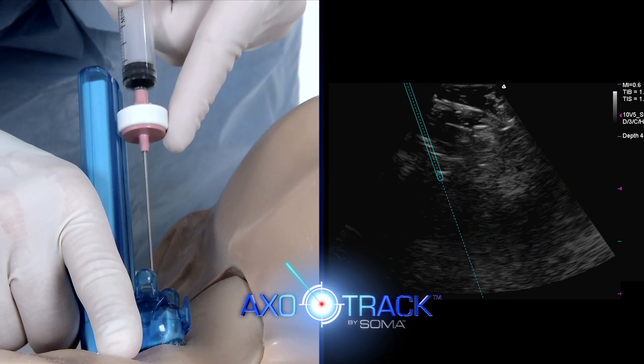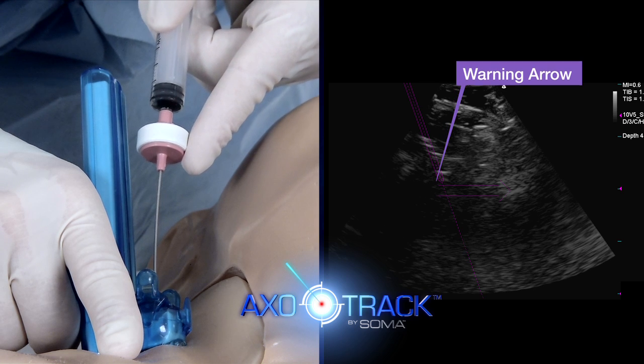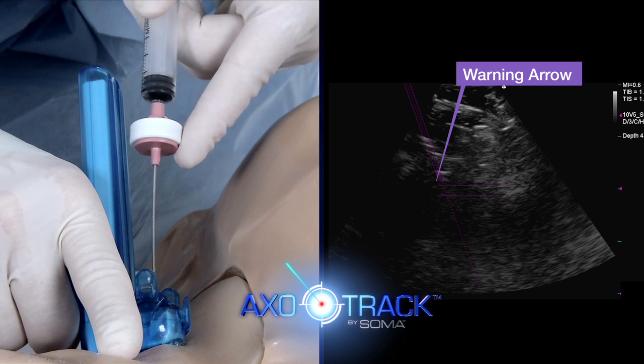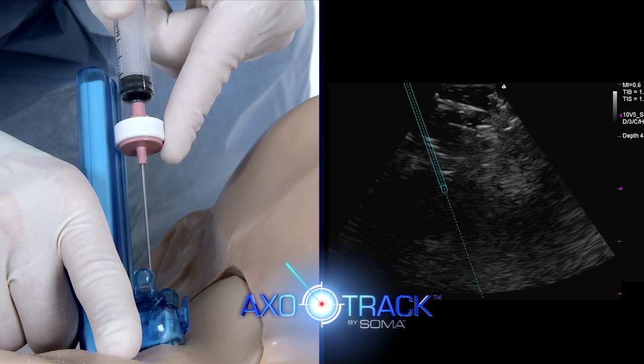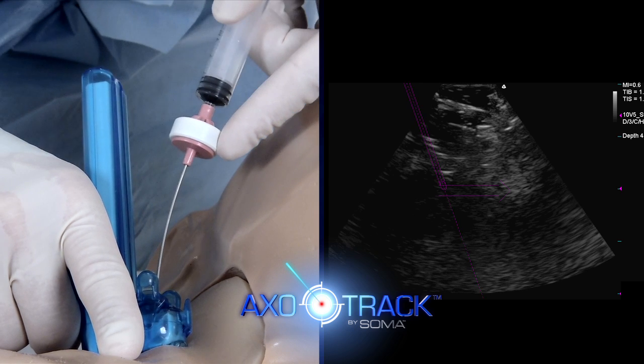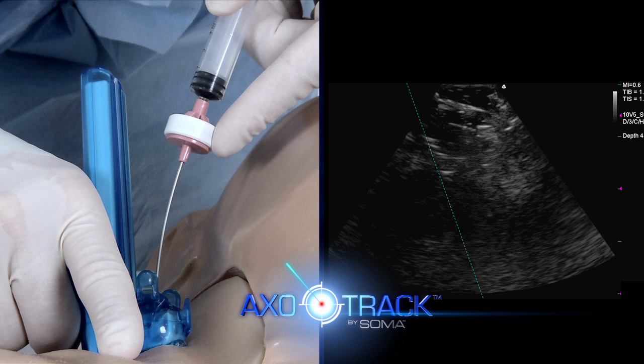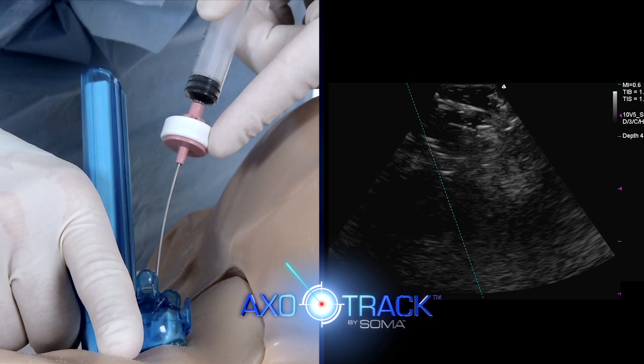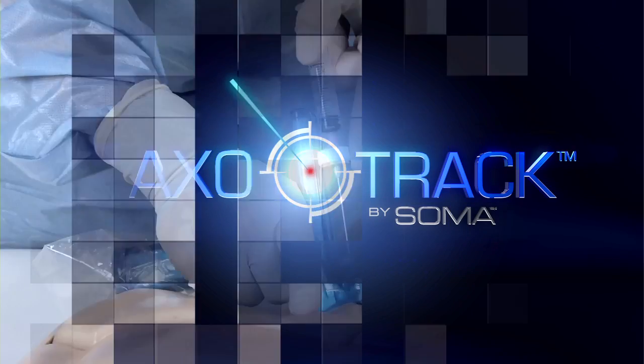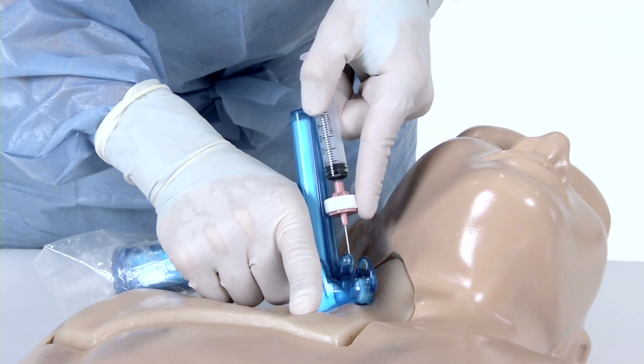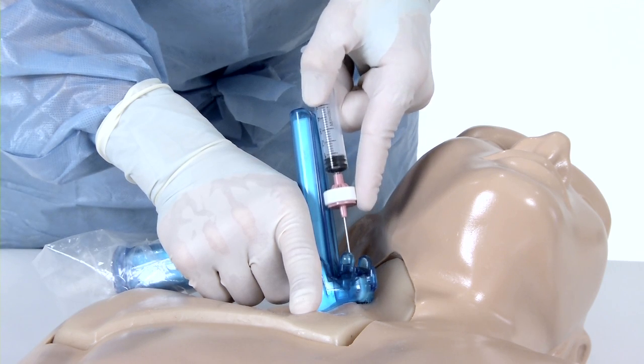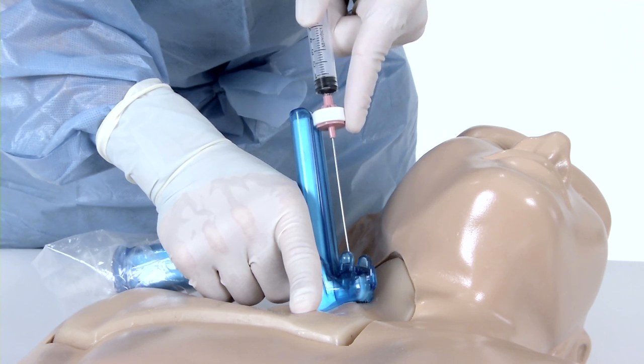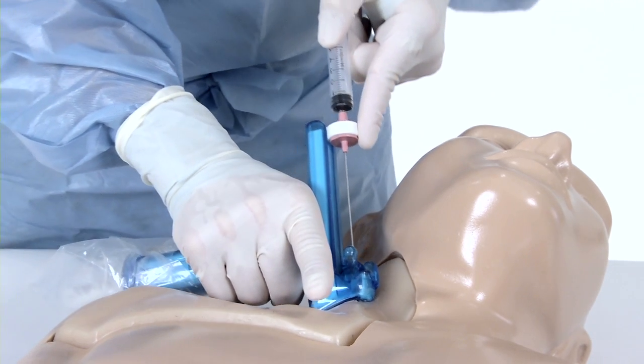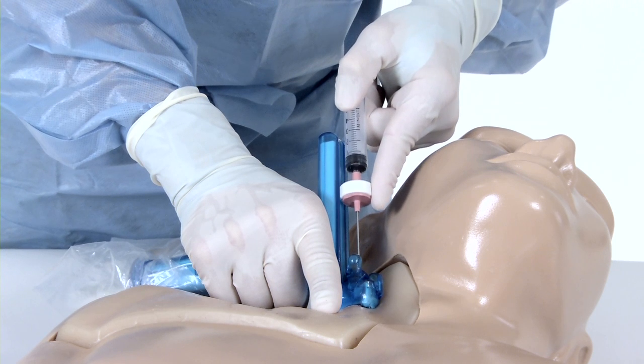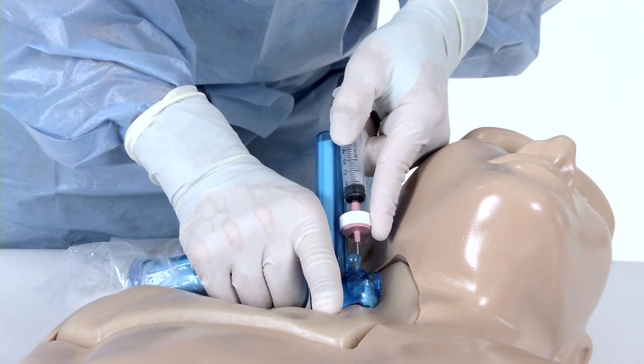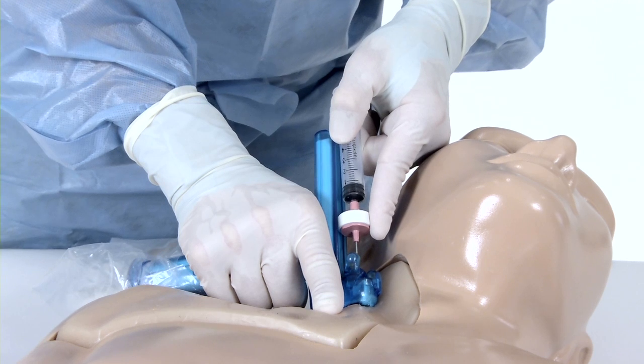If the magnet is bent away from the magnet rail, a bold warning arrow will appear on the sonogram, indicating that the magnet should be returned to its proper location. If the needle is bent too forcefully away from the magnet rail, the virtual needle will disappear completely, preventing continuation of the procedure. The practitioner should not attempt to reposition the needle or target line without withdrawing the needle to the skin surface. Once this is done, it will be safe to realign the target line and advance the needle to a different target. Correct needle position must be confirmed by the appropriate clinical indicator.